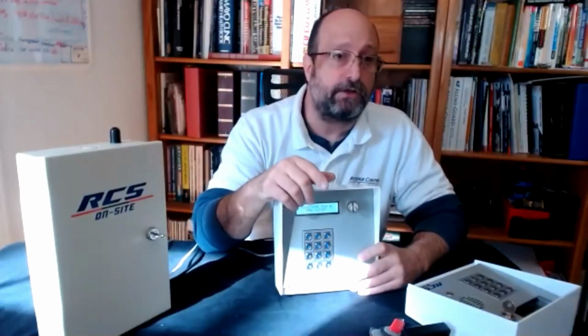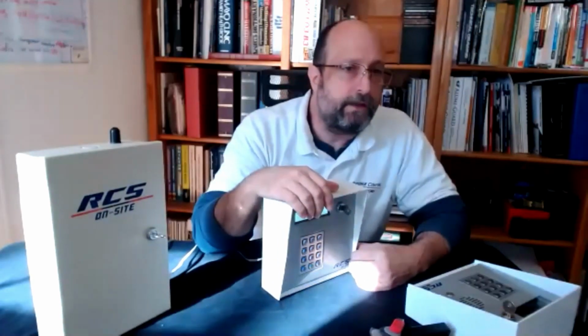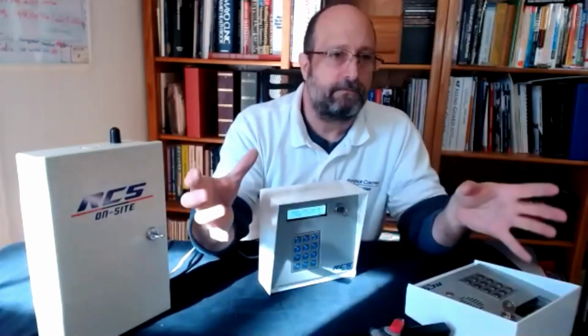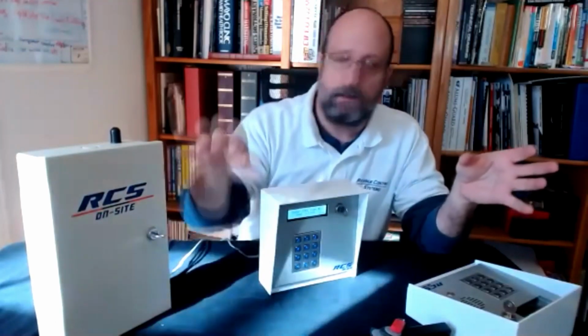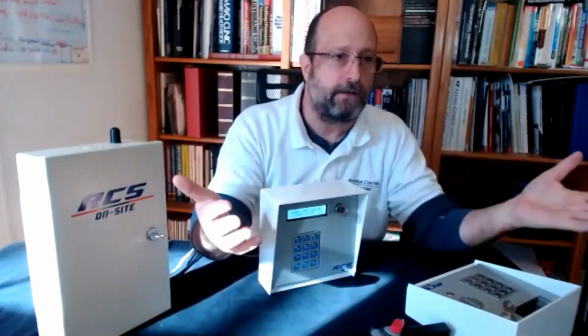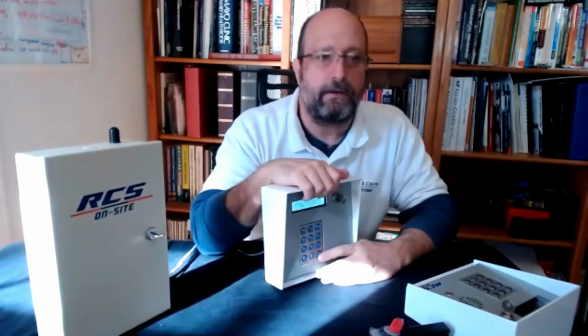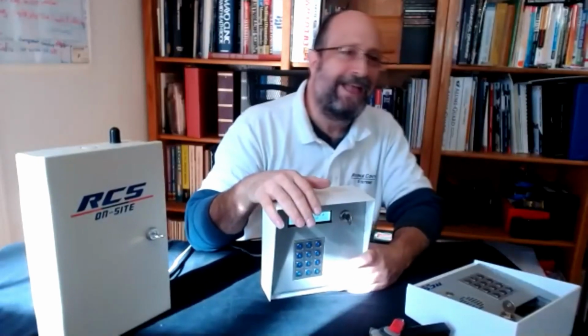Now, additionally, if you have a site you're bidding or quoting on and you're unsure, we can send you a pair of testers. You put one tester in the office where the controller is going, and you take the other tester out to the location, you hit the button, and it'll tell you if you've got signal. So you'll know right away if it's going to work or not. We could ship you the ones we've got, or we could tell you how to get your own. You let us know if you get to that point. Matter of fact, you might already have them.